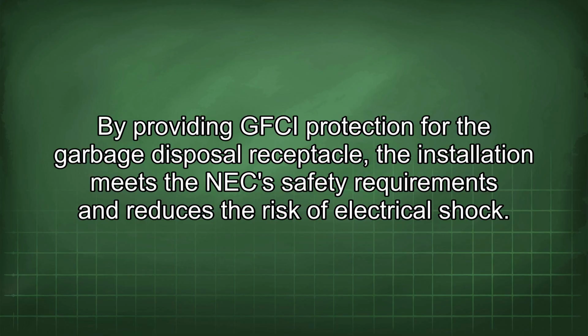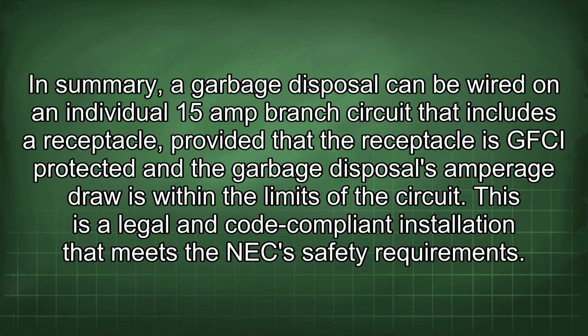of electrical shock. In summary, a garbage disposal can be wired on an individual 15 amp branch circuit that includes a receptacle, provided that the receptacle is GFCI protected and the garbage disposal's amperage draw is within the limits of the circuit. This is a legal and code-compliant installation that meets the NEC safety requirements.